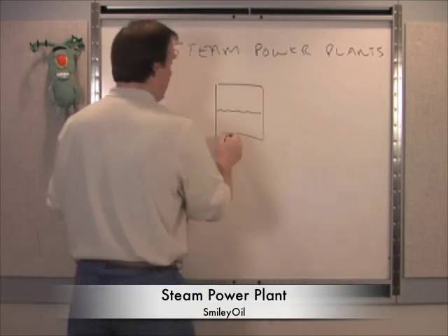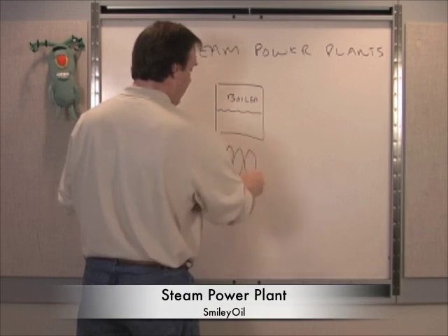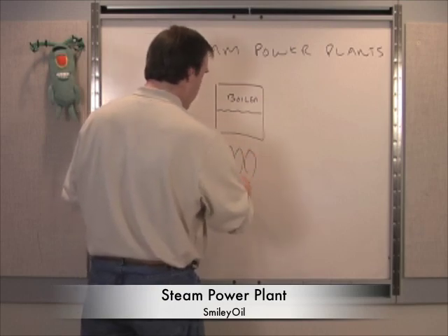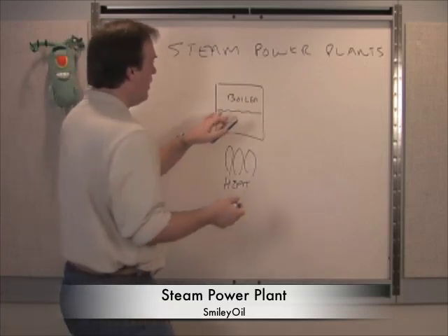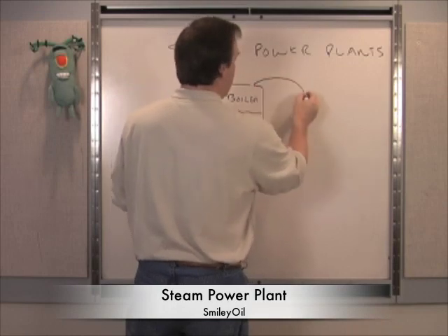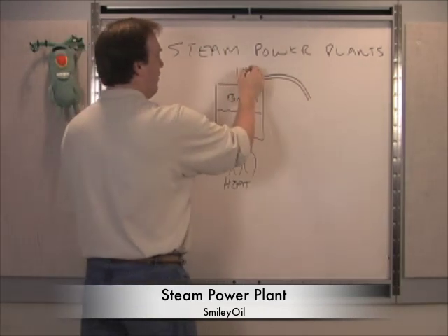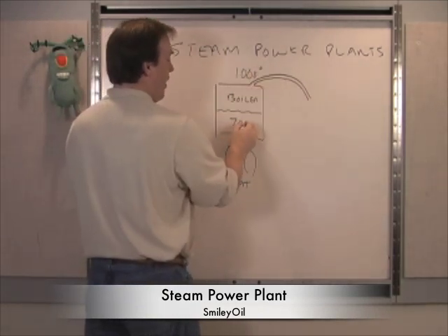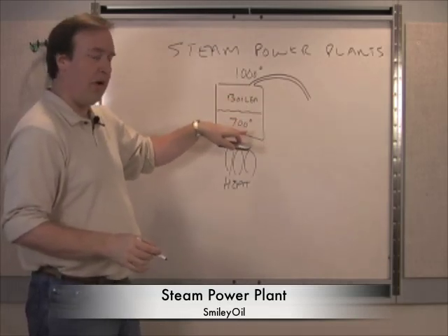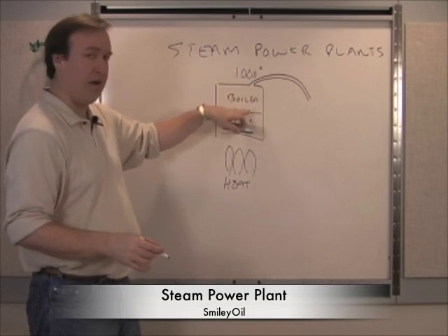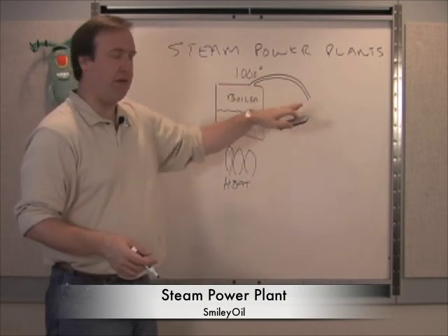and we put water in it. This is our boiler. And we put heat, flame, underneath it. Now, if we don't do something, this will explode. Well, the difference between a boiler and an exploding paint can is we take the hot 1,000-degree steam. The water is at 700 degrees because it's under pressure, and water doesn't boil at 212 if there's pressure on it. It can go up as high as 700 degrees. We try to take this as high as the metal can go.